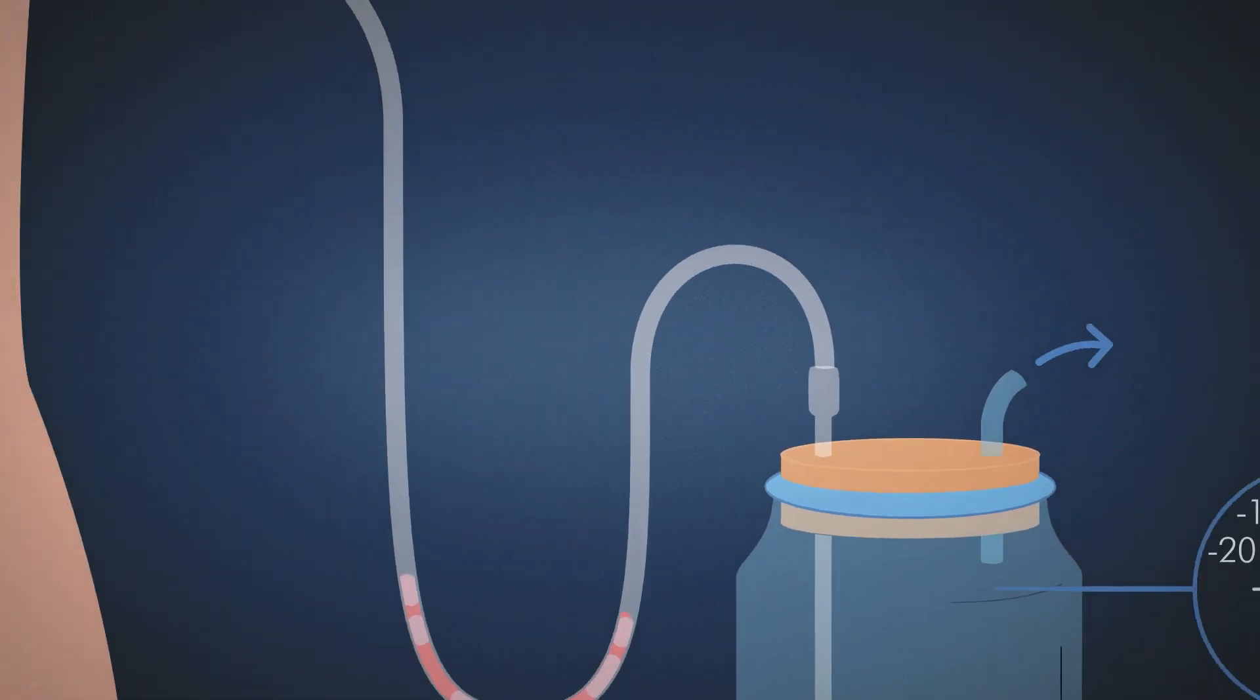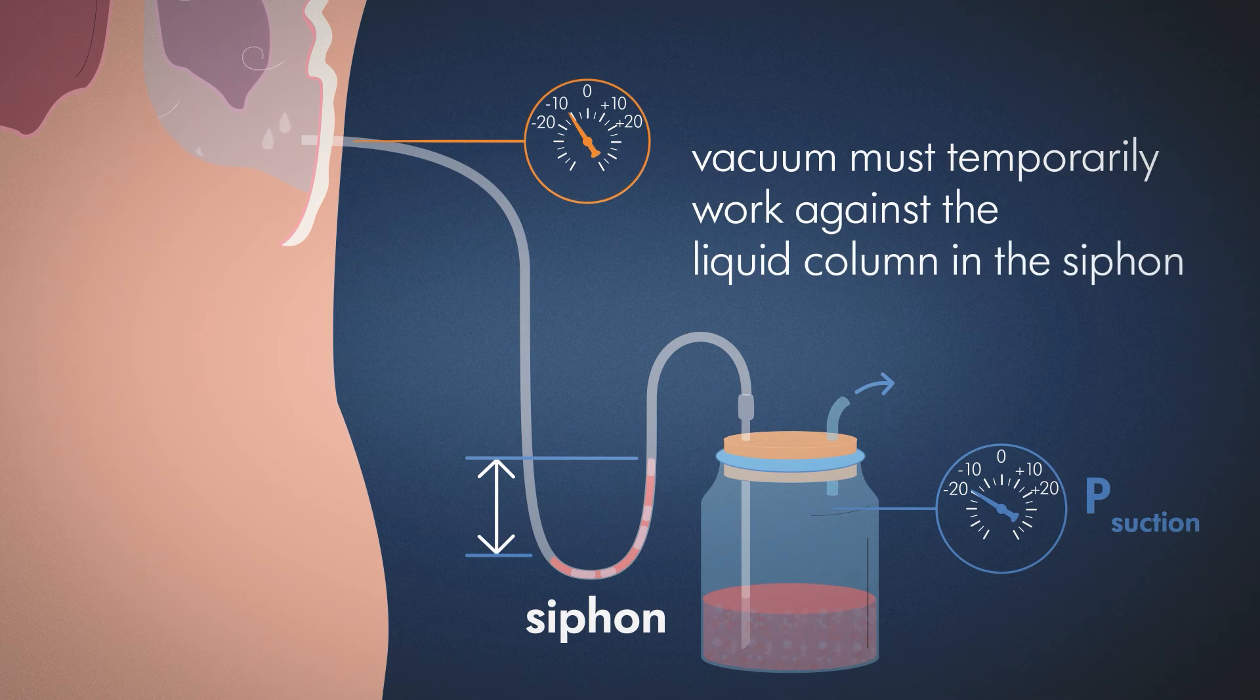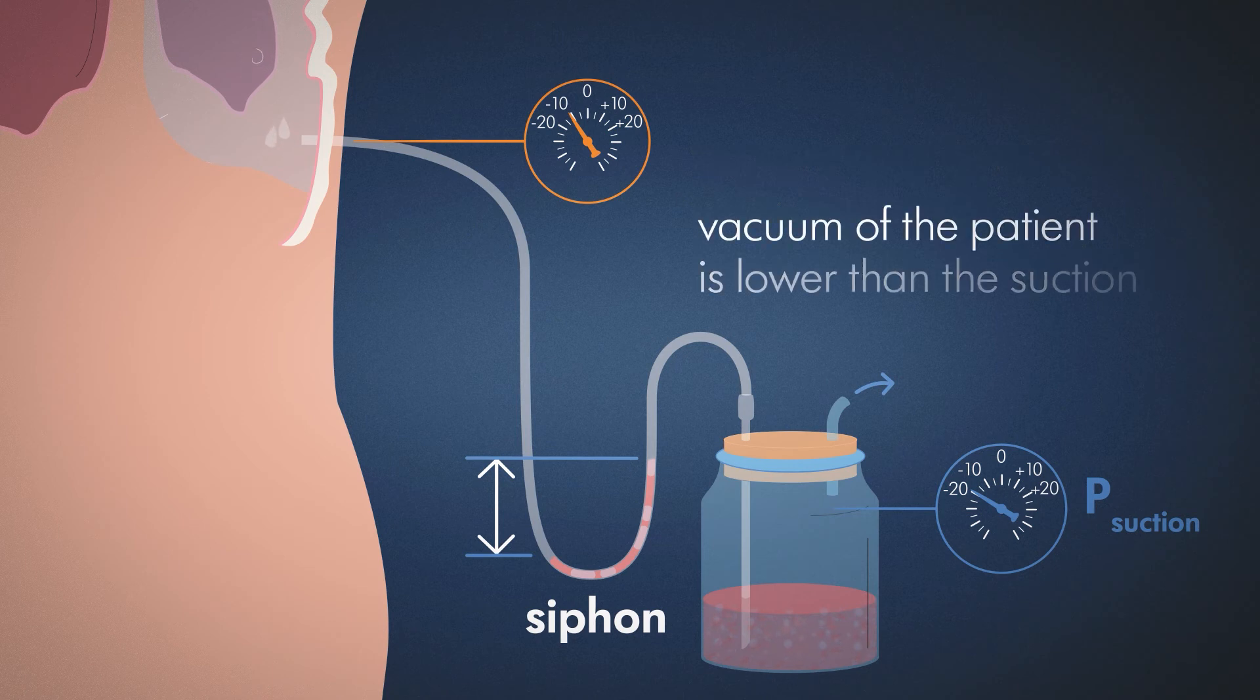A siphon can form if the tube sags between the patient and the drainage system. If the drainage hose carries both liquids and air, the vacuum set on the unit side must temporarily work against the liquid column in the siphon. The vacuum applied to the patient is then lower than the suction applied to the device.